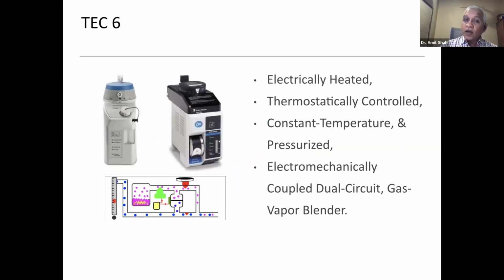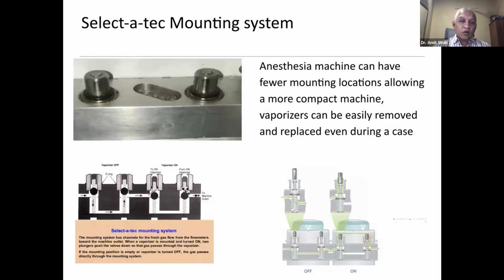So, desflurane vaporizers are electrically heated and thermostatically controlled. They have a constant temperature and pressure. They are electromechanically coupled, a dual circuit gas vapor blender. So, it is a gas vapor blender. Now, three important points. Selectatec mounting system.